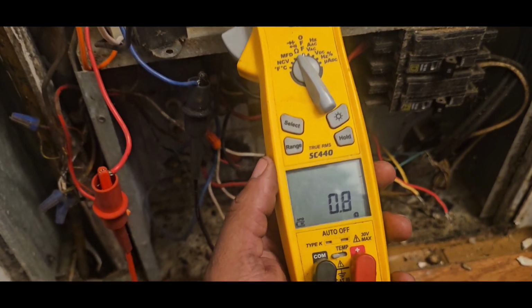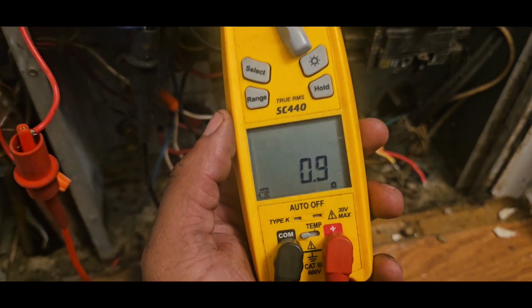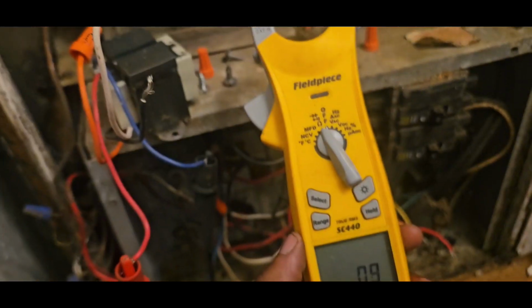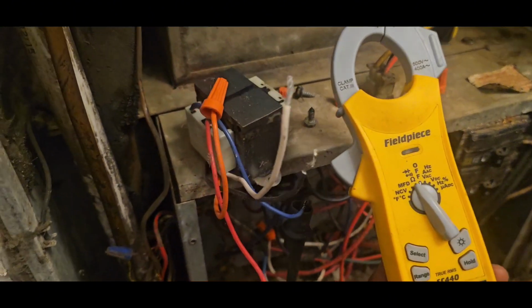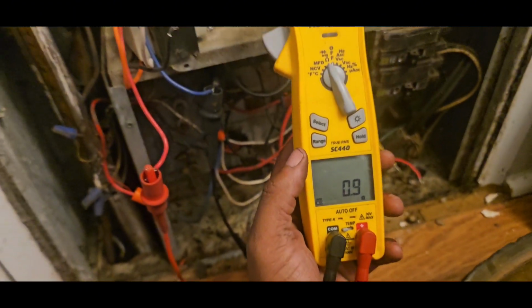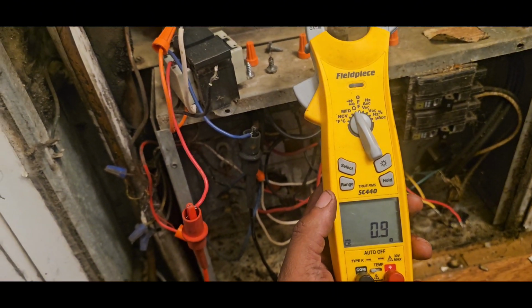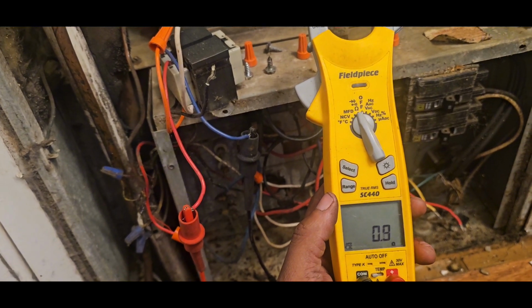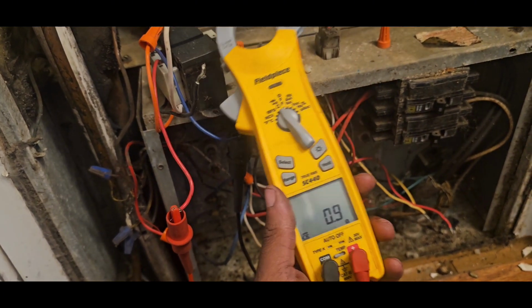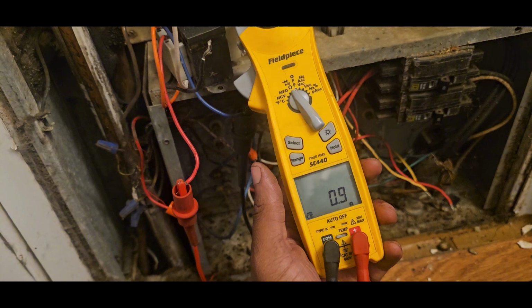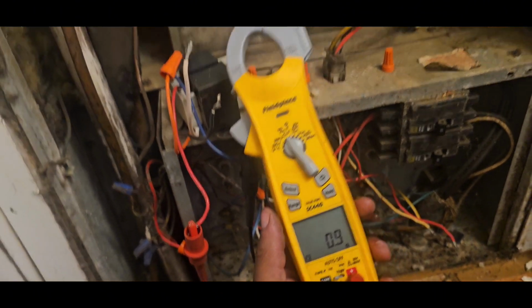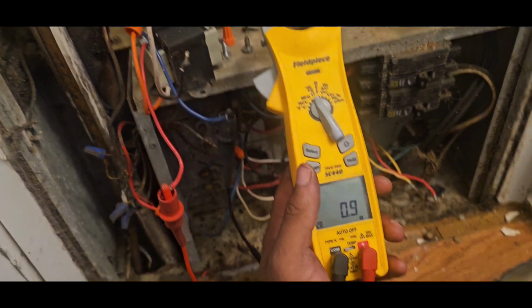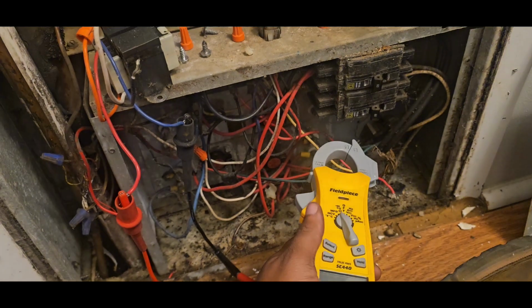Now I've got my meter set to ohms, but it's reading 0.9, which I think is too low for the low side of a transformer. I'm gonna go double check outside with a new one, but either way, I had no voltage, no low volt coming out of here, but high volt going into here. So I definitely, first thing got to do is replace this transformer and then figure out what else is wrong with the system.